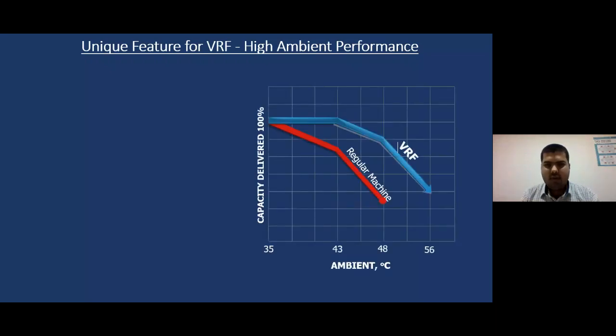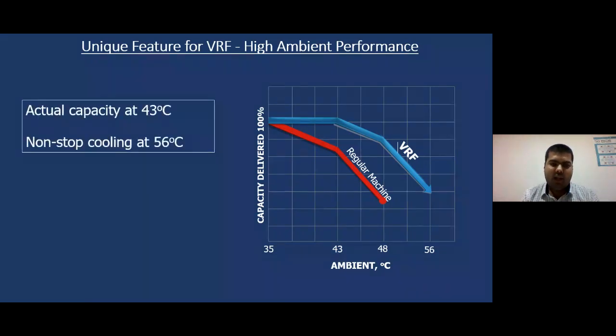So what are the unique features of VRF? High ambient performance. What is the basic comparison between a VRF and a regular machine? As I said earlier, VRF works at its actual capacity up to 43 degrees Celsius, whereas the regular machine is designed only at 35 degrees Celsius. As you can see in this graph, a normal machine would start derating after 35 degrees Celsius, and after 43 it would derate a lot. But in the case of VRF, up to 43 the machine does not derate. It gives complete capacity up to 43, and after that the machine will derate, thereby increasing power consumption, but it can work up to 56 degrees Celsius.